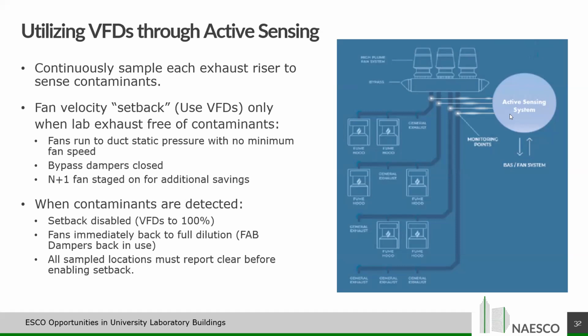Now it's continuously sampling the air. And if that air does then get volatile, you get some hazardous chemicals in there, it'll immediately shift over to the fresh air bleed system again. The VFDs go to 100% speed. The bypass dampers go into control to control constant static pressure. And you're now back up to your 3,000 feet per minute discharge velocity.